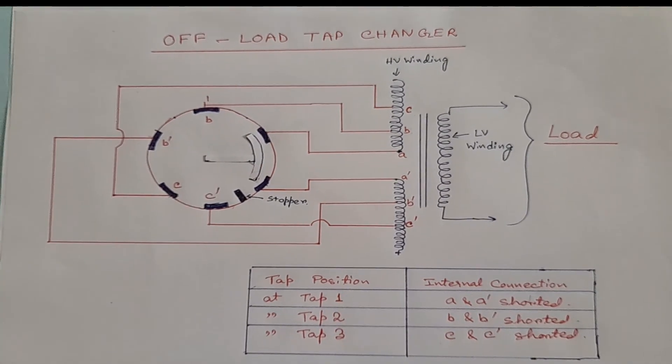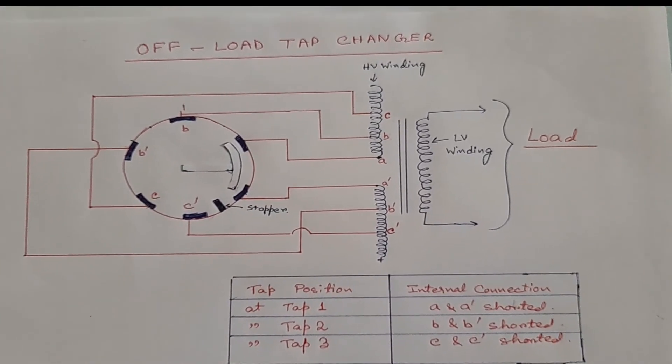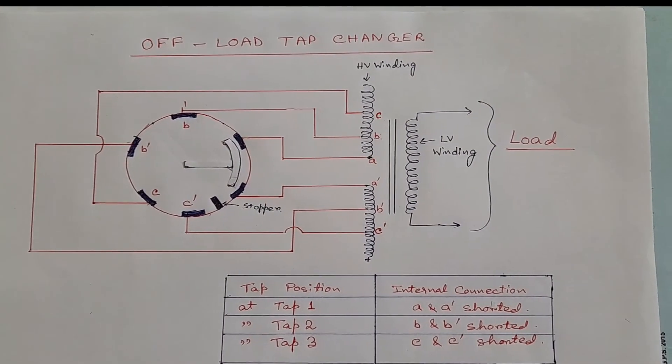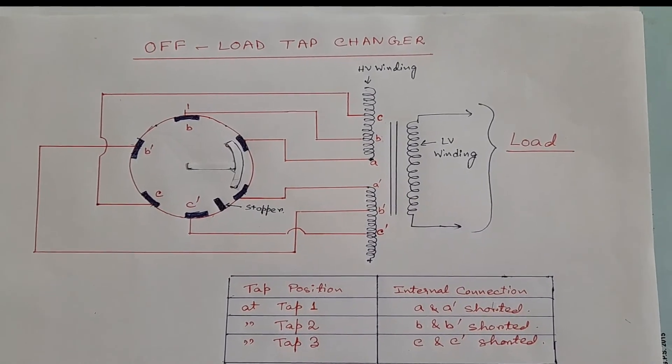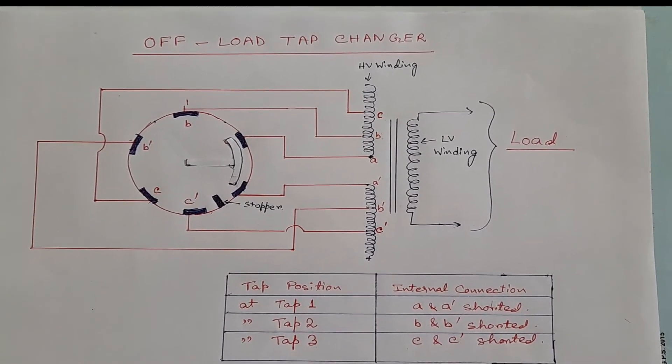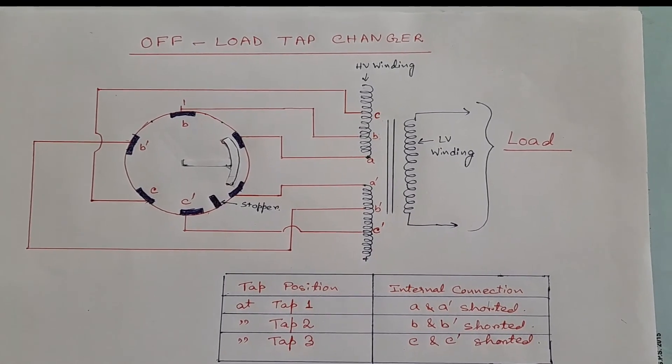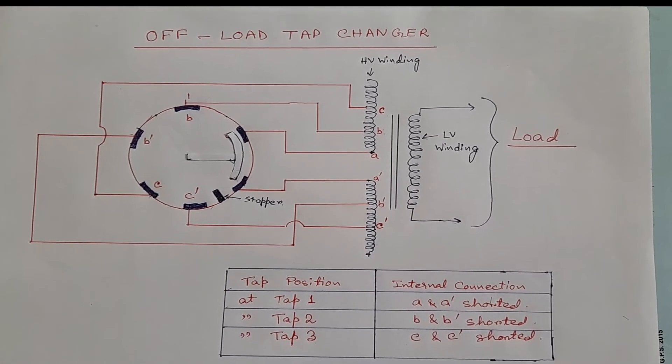But this tap changing operation should be performed after switching off the load, because in a tap changing operation by an off-load tap changer, there will be a momentary discontinuity between the upper and lower winding of this transformer.